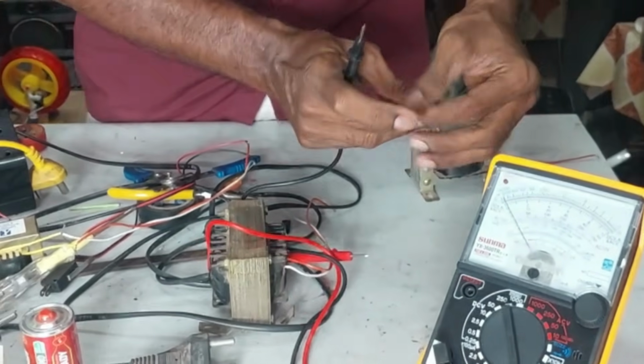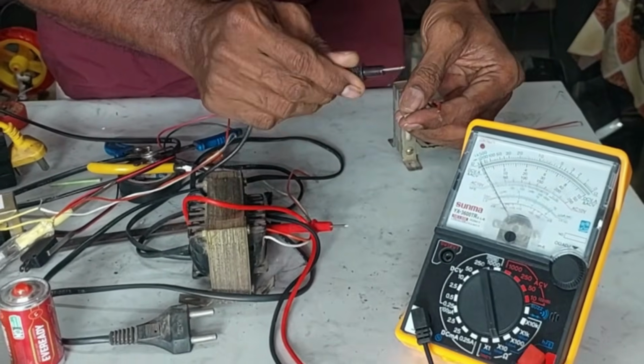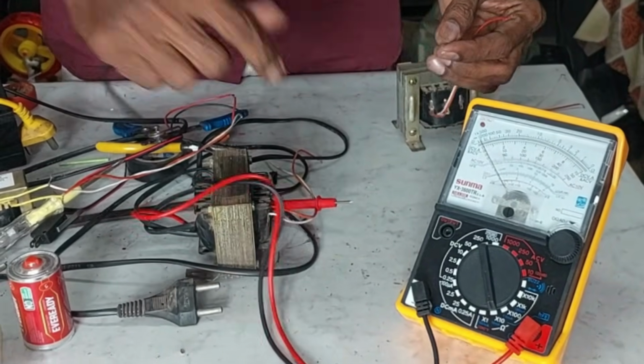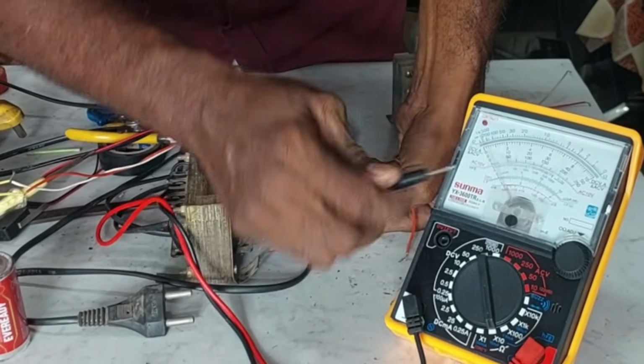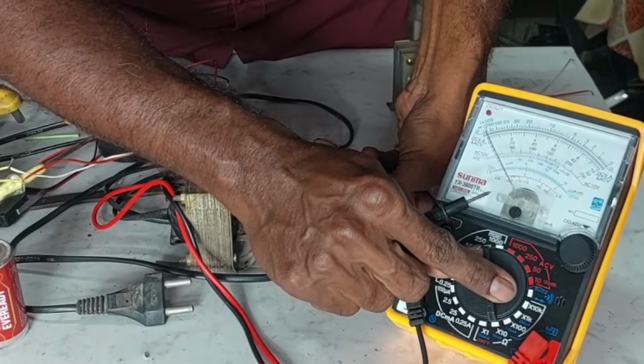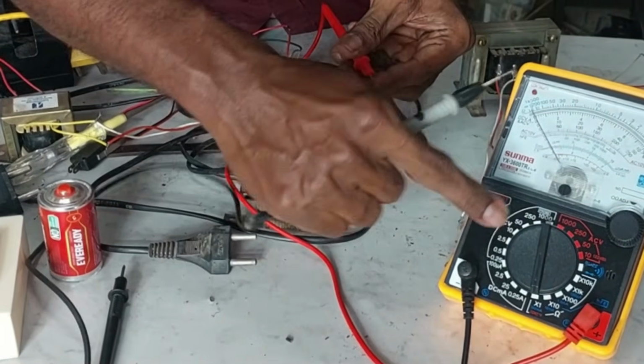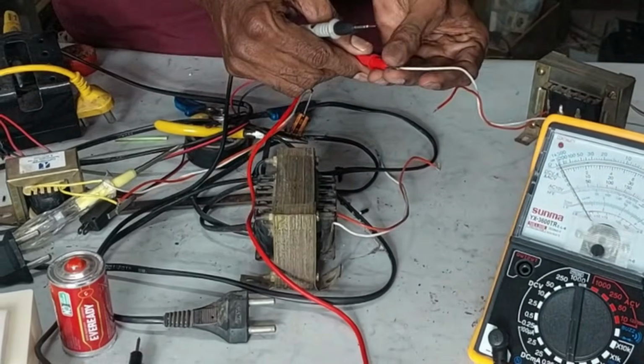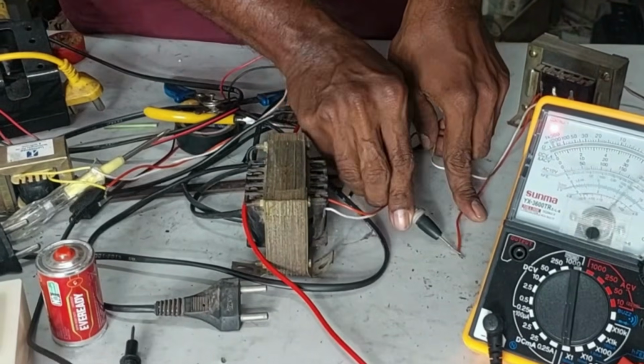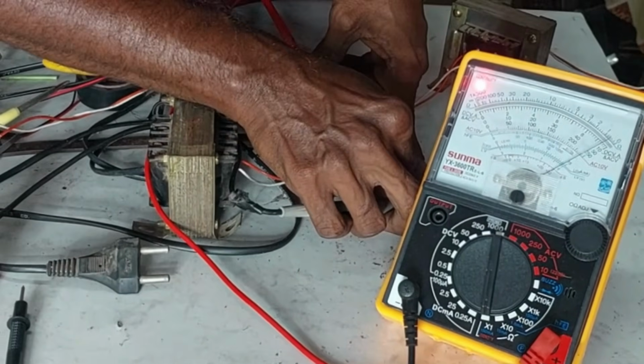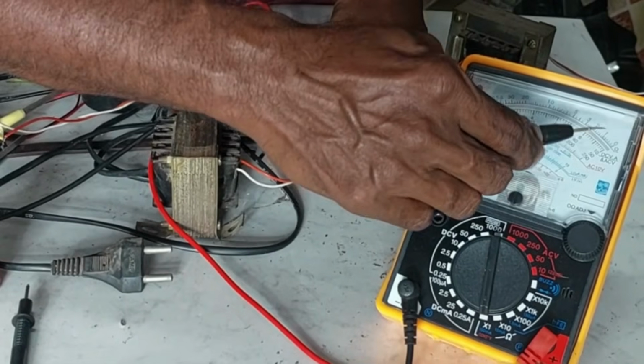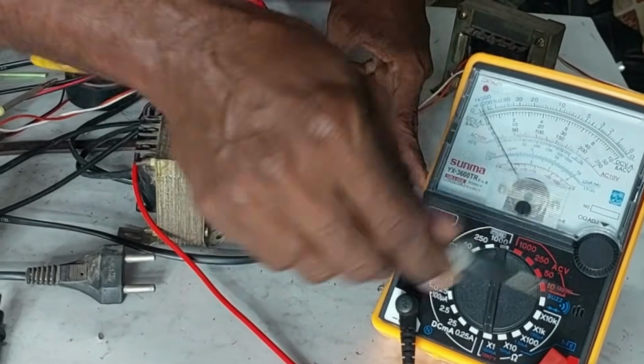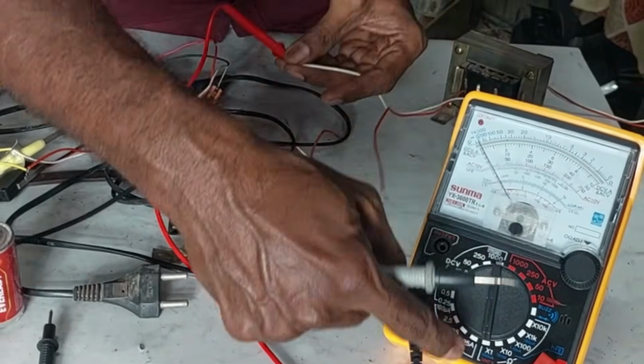This is the primary, 230 volts AC. Now let us check the other side. Since the resistance is low, set the range to 1. Again adjust to 0. Now it shows around 5, so 5 multiplied by 1 gives 5 ohms. This is the secondary, 12 volts AC.